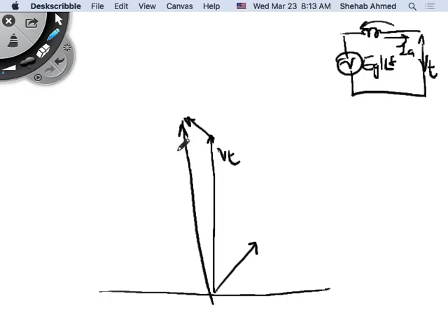We also talked about limiting the leading power factor. The way we drew the phasor diagram, VT was the terminal voltage, and EG at angle delta was the internal back EMF magnitude. We took the armature current, added the voltage drop, and calculated the corresponding E and delta for any given current. This is for the lagging power factor case.